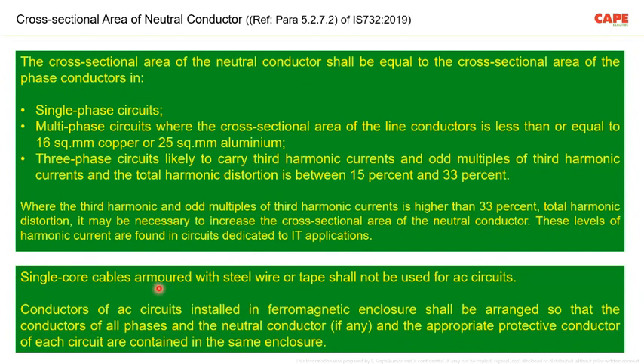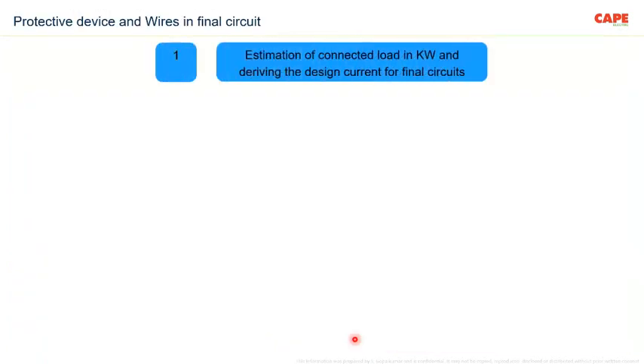Single phase, single core cable armored with steel wire and tapes is not to be used in an AC circuit. Conductors of an AC circuit installed in a ferromagnetic enclosure shall be arranged so that the conductors of all the phases and the neutral conductor and the appropriate protective conductor of each circuit are contained within the same enclosure. Of course, these are the additional requirements.